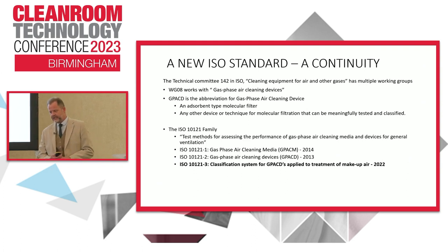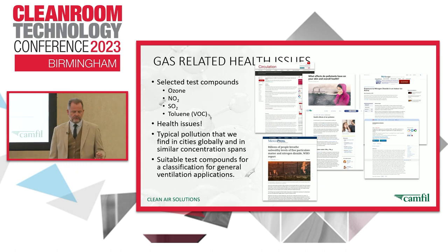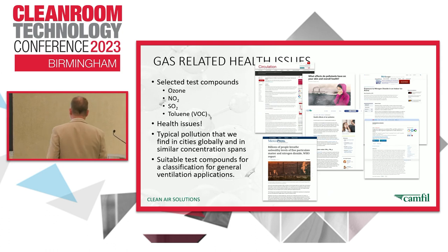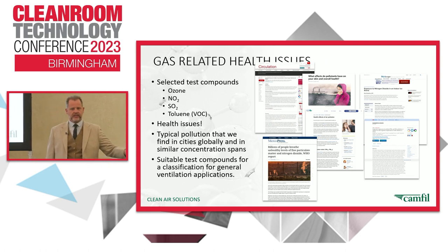It's a new ISO standard - a continuity of some standards that were out there. Technical Committee 142 for cleaning equipment for air and gases had multiple working groups and they published this last year. It will affect standards like the Eurovent standard, some of the REHVA guidelines, and ISO - what was EN 13779, now renamed. These are standards directly related to ventilation of buildings to control molecular contamination. During the pandemic we had reports on viral load, viral contamination. Publications now talk about molecular contamination: ozone, nitrogen dioxide, sulfur dioxide, toluene and VOCs. These have been spoken about for many years but never regulated other than on factory exhausts - not in the city, not in the school, not in the building, not in the clean room.